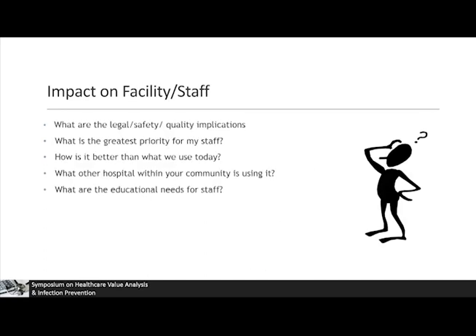So what's the impact on your facility and staff? What are the legal, safety, and quality implications? If the product is not used according to the manufacturer's instructions for use, or MIFU, we typically just say IFU, the device warranty may be null and void. What I mean by that is if you use a particular product and you do not follow the IFU, and you use something to clean the device that is not actually part of the IFU, that will null and void your warranty. You must always look at the IFU to ensure that you're using the appropriate cleaning disinfectant product on it.